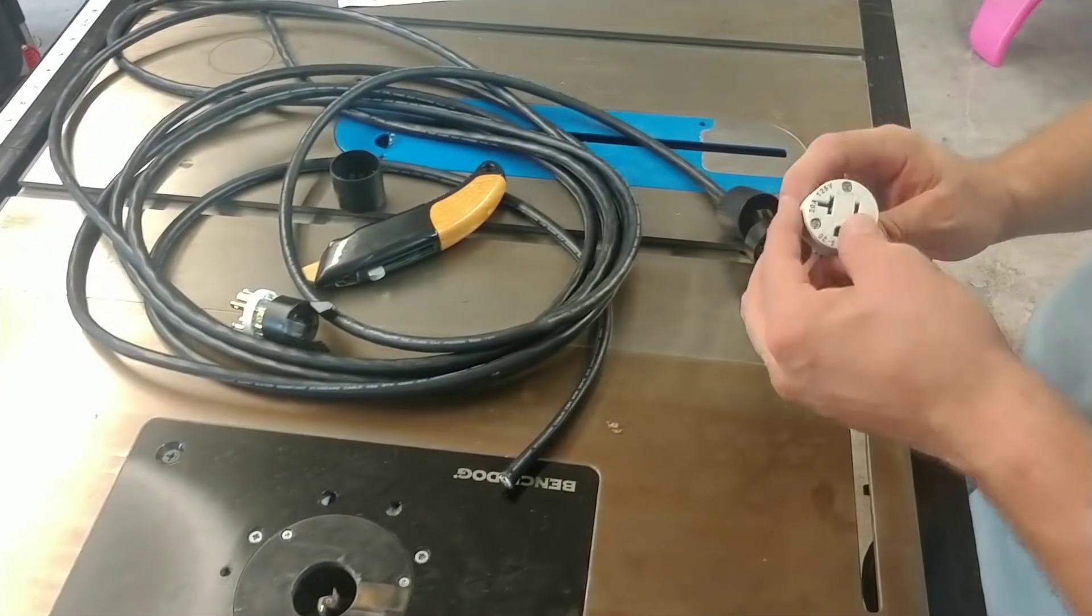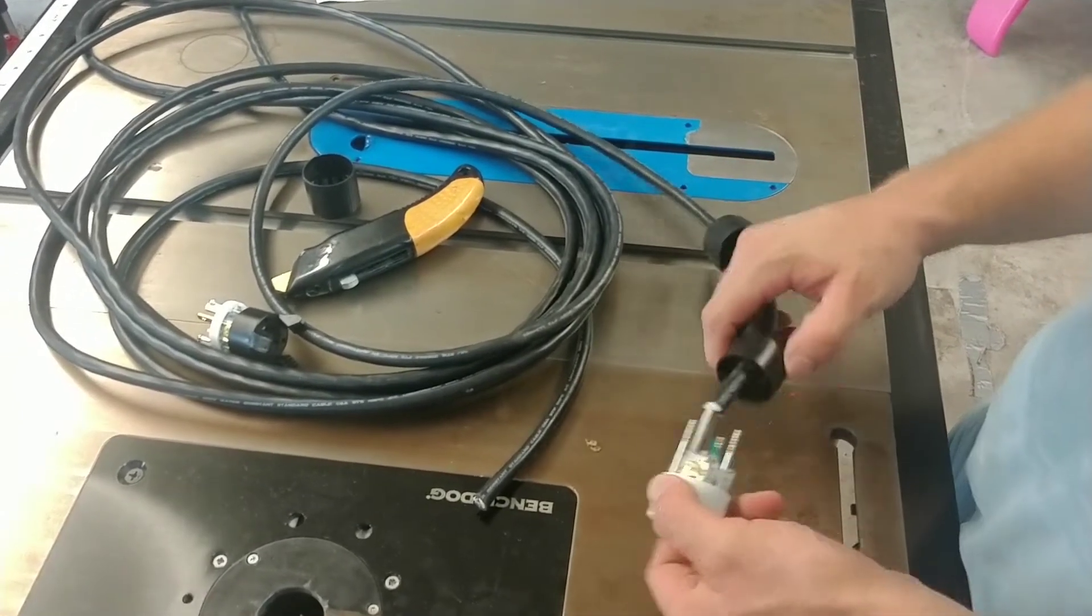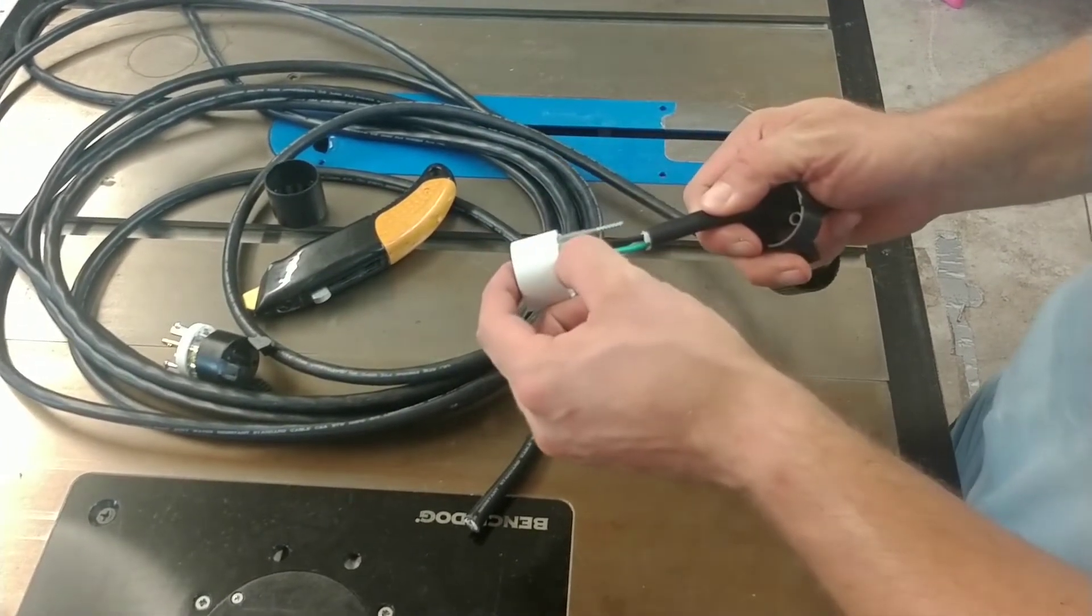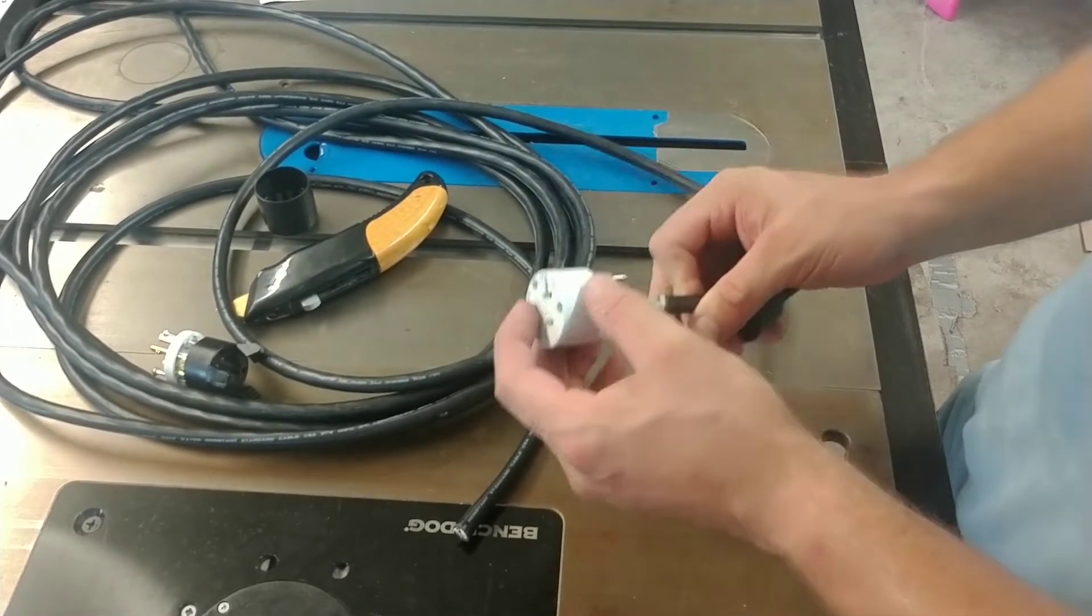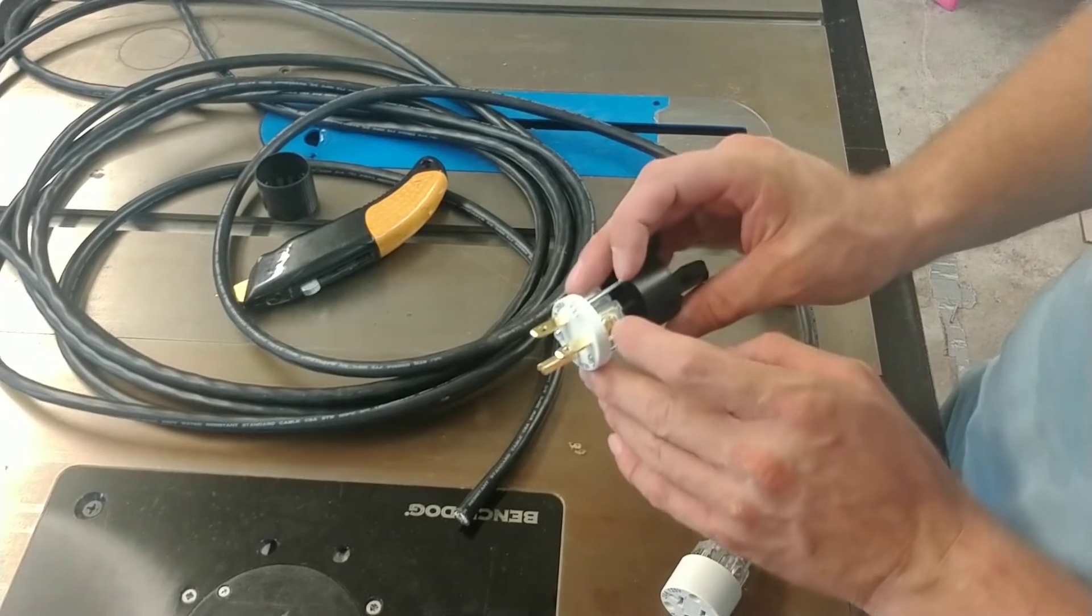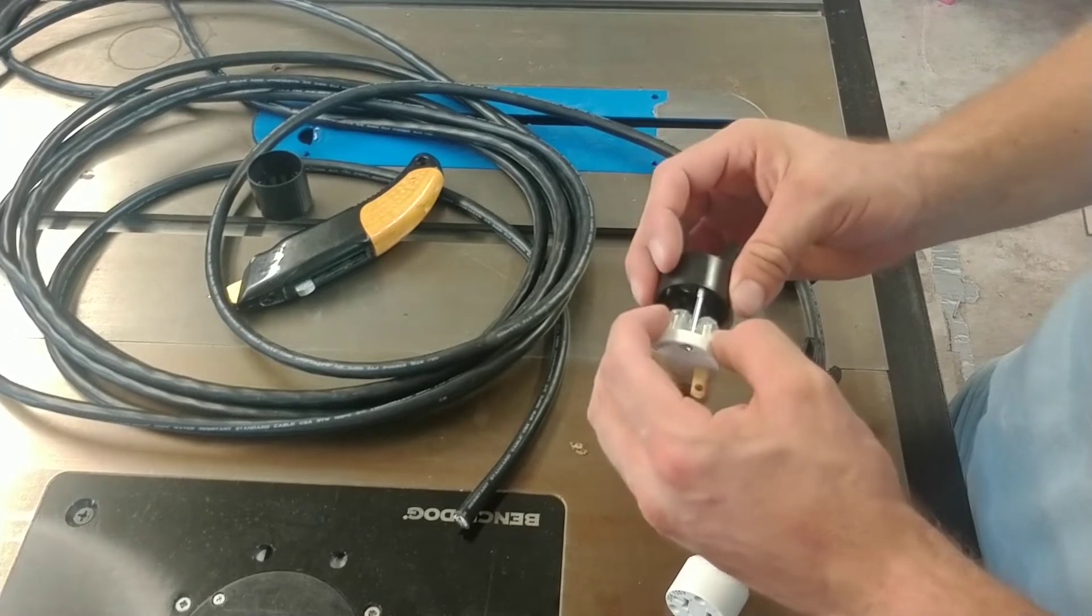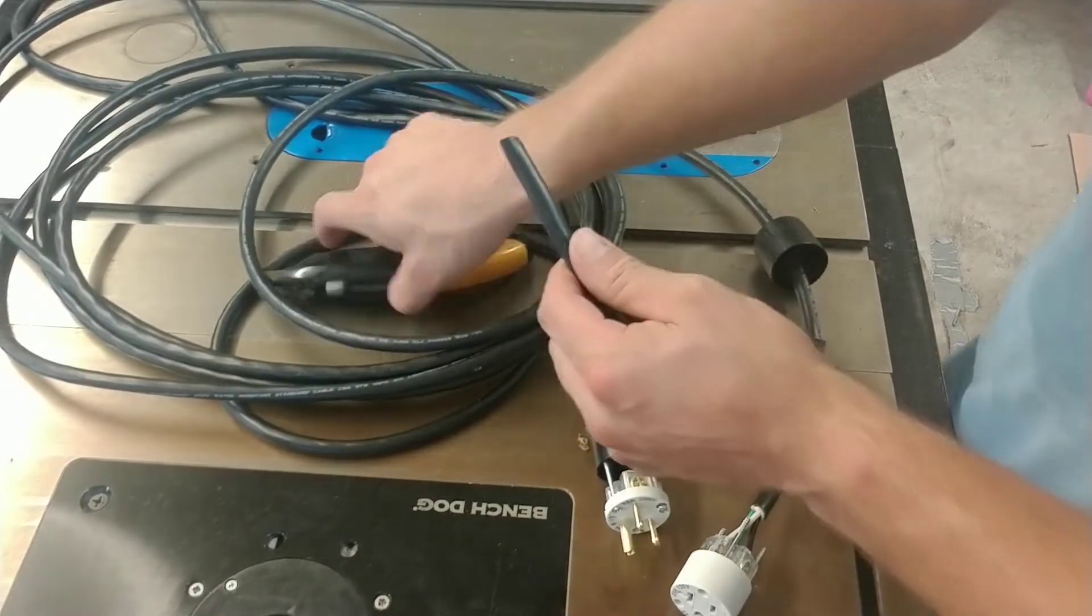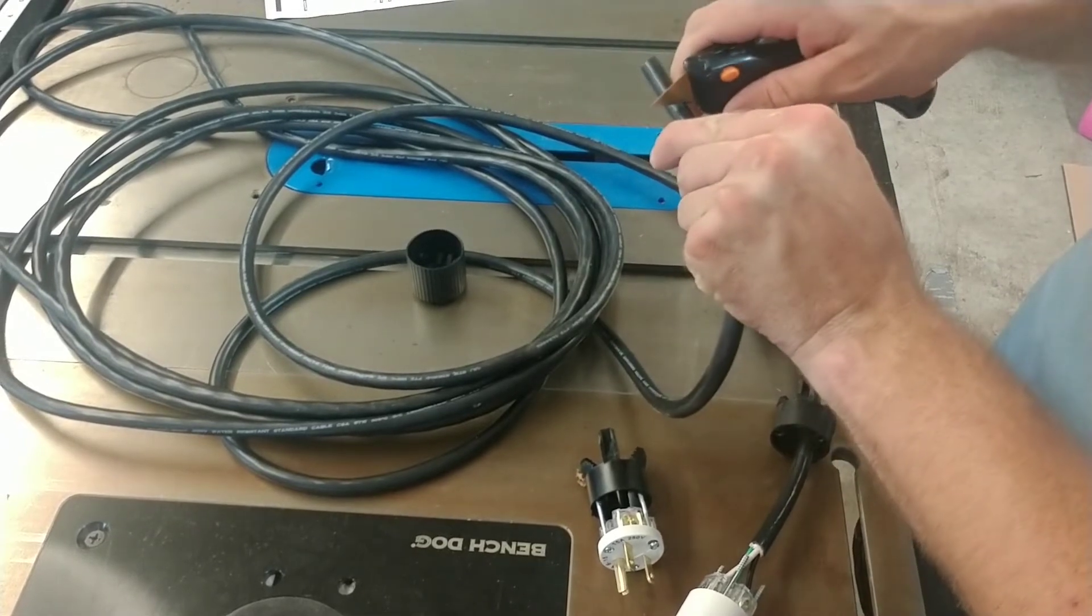Okay, so in terms of building the cord for this, you got a 120 volt female outlet cord cap. On the brass colored one, you're going to put the black wire. On the zinc or green one, you'll put the ground. And then neutral is going to go on the silver screw on the other side. The only one that really matters is that you get the ground on the green screw. In order to make this up, you basically want to go back about an inch, just lightly run a razor along the outside of the insulation, and then you can pull this back.